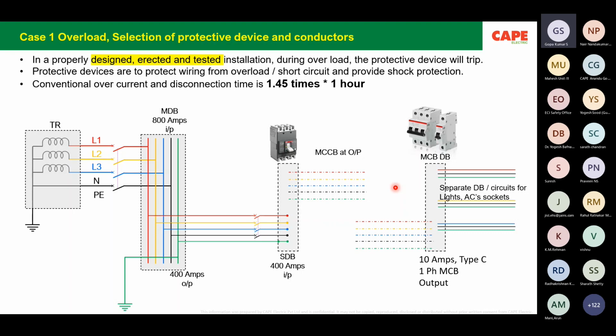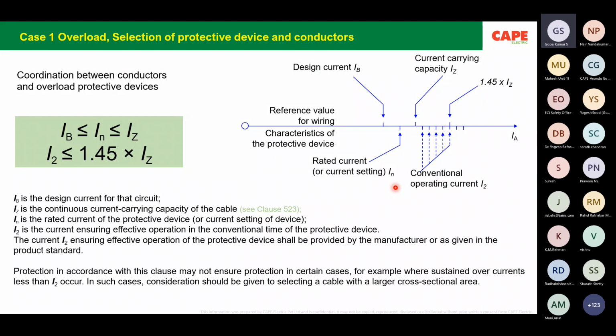Selection of wiring, selection of the protective device, and type of the protective device are very much important. So there are tables included, especially in part 1, section 10. You can find these pictures. Also, please note that NEC has to be read along with IS 732. A lot of information in IS 732 we didn't reproduce in the National Electrical Code. It always says you have to read the clause dash dash of IS 732. So you have to refer to IS 732 as well. Now, these pictures explain how to select the wire and how to select the protective device to ensure safety.